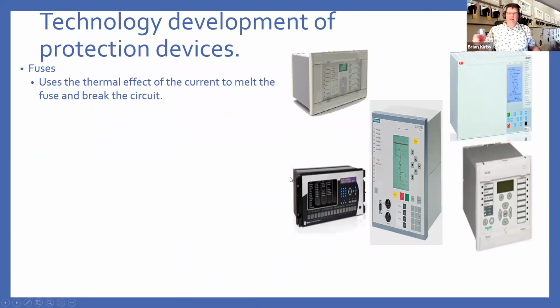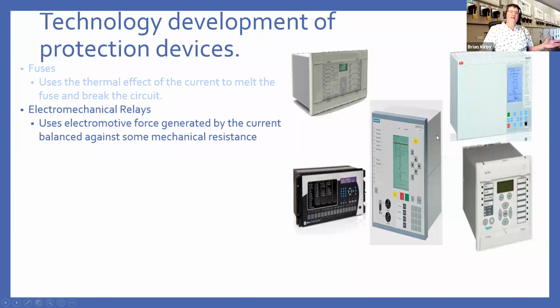So, as I've mentioned, in order to achieve protection, we have standalone devices. So the earliest elements were fuses. They will isolate if you get excessive current, but then you have to have someone go along and replace it to reactivate your system. So to overcome that, the earliest devices used electromechanical forces. So generally the current would generate electromotive force in some sort of mechanism, and then you have some sort of mechanical resistance, say a spring, which would resist it. And if your current got sufficiently high to overcome that, it would activate contact and operate your protection. And then when the current cleared, that would then release the trip signal again, so the line could be re-energized.